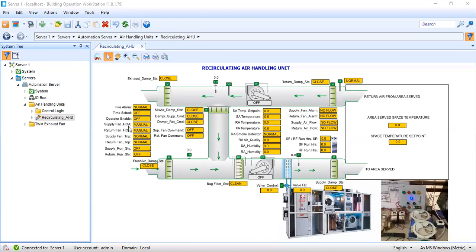What are the physical points? I have here the hand/off/auto, trip and run status, and the command. This is my return fan command and supply fan command. As you can see, I have a picture of an air handling unit. Here I have the supply fan as depicted by this fan in my graphics, then the return fan as shown by my graphics. The same simple motor control I will be using to control the supply and return fan.